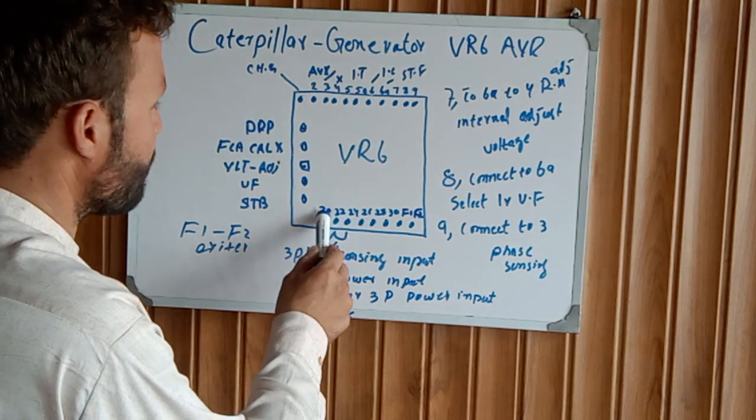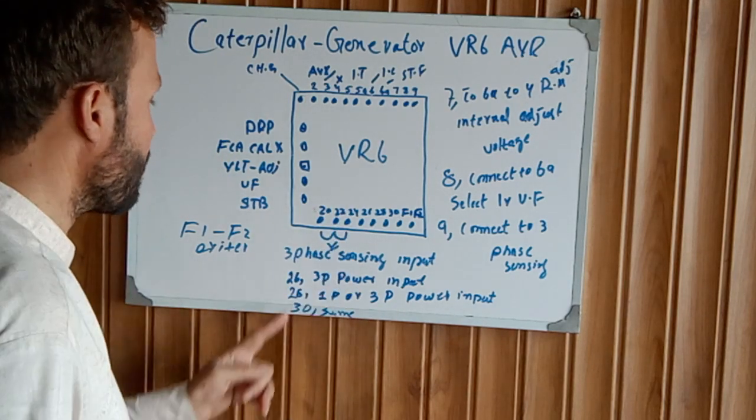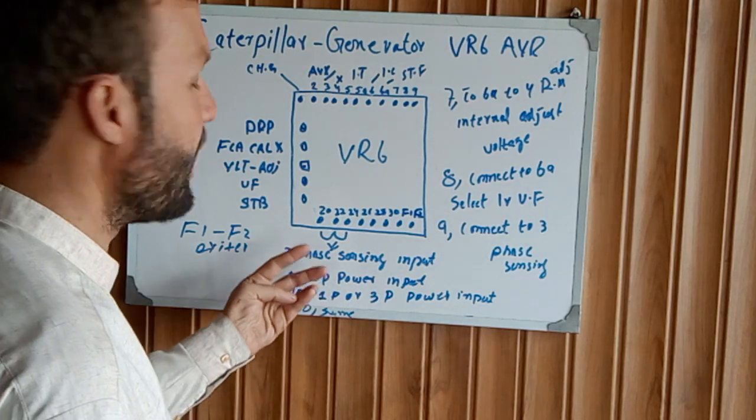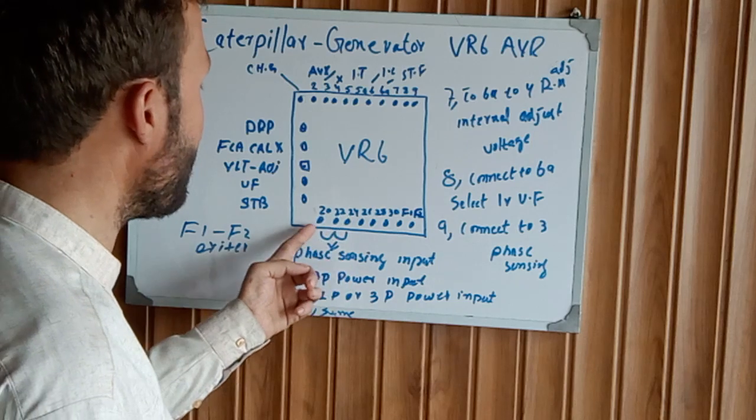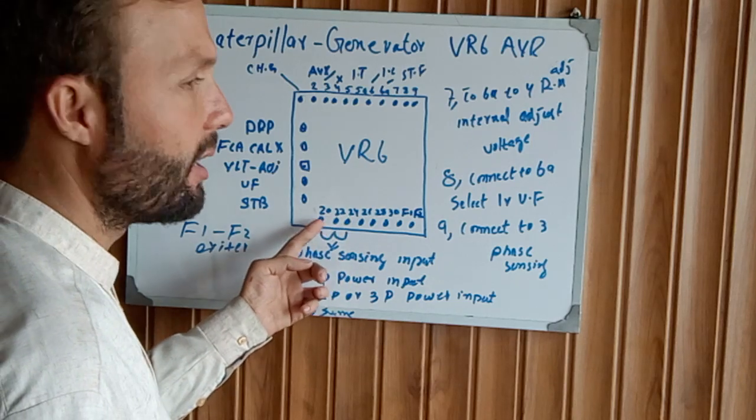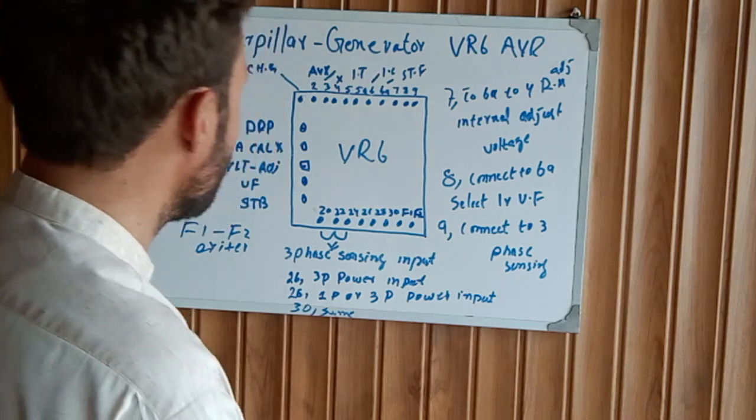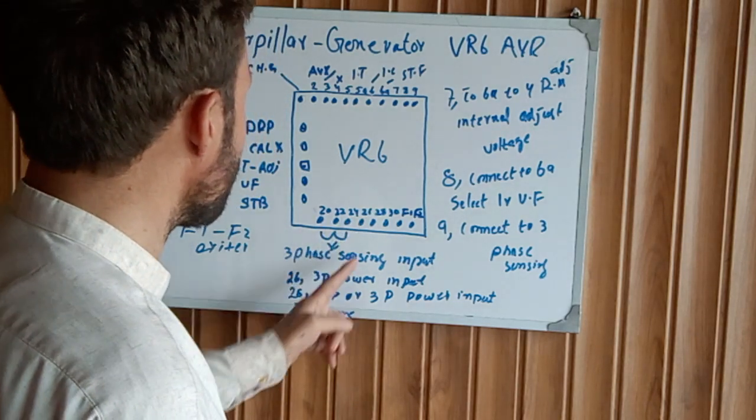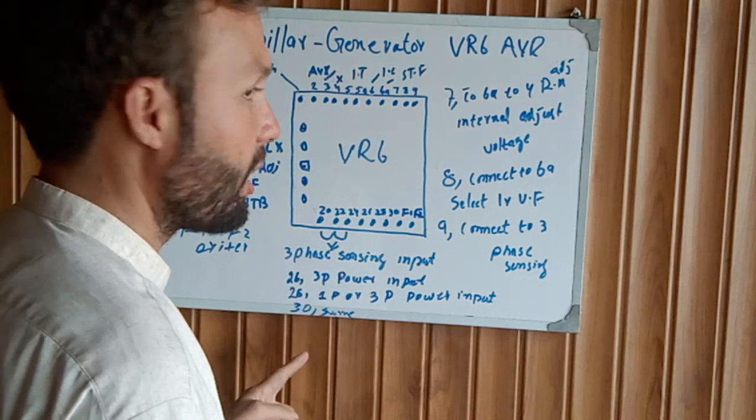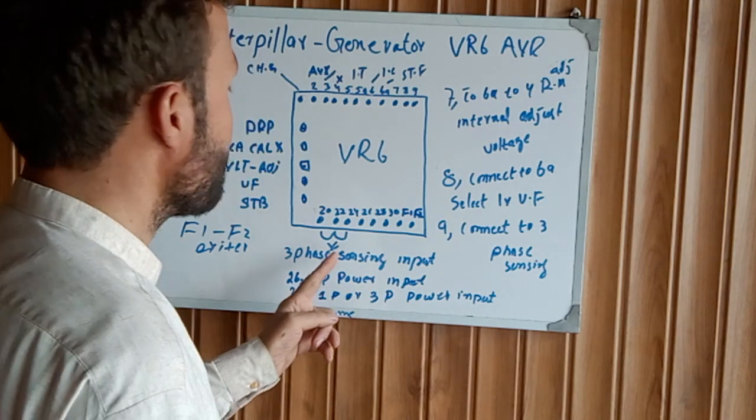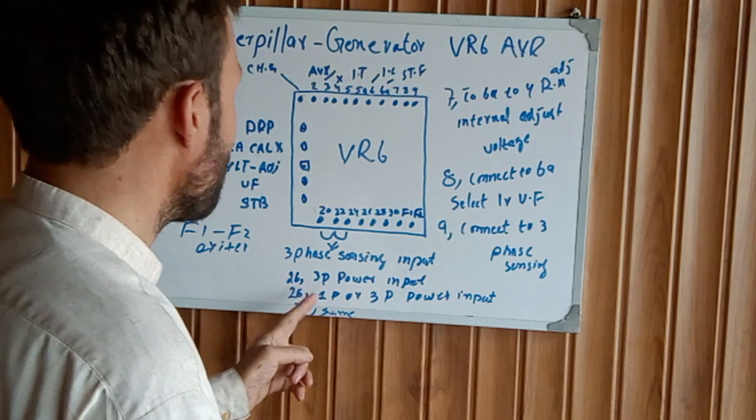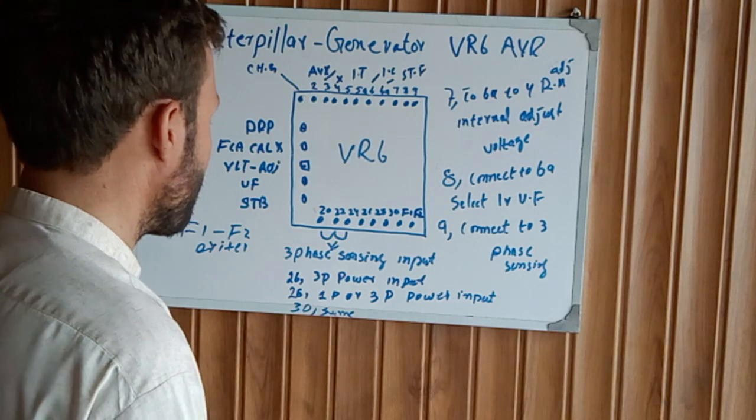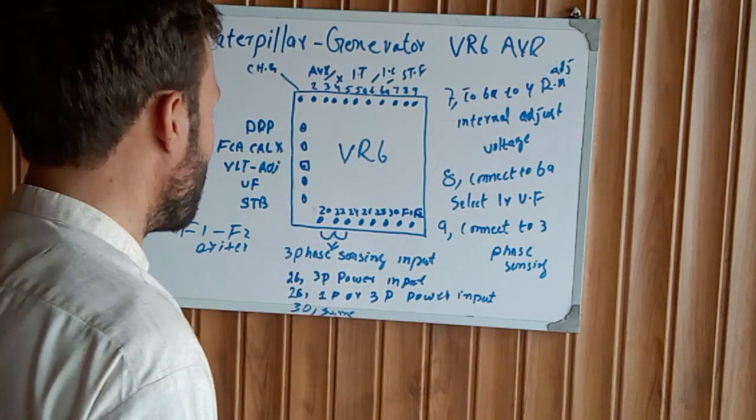After that, there is 20, 22, and 24. Three-phase sensing input. Like L1, L2, L3. Like A, B, C. Like X, Y, Z. Three phases of the alternator input sensing. 26, three-phase power input. Take one wire from the phases and connect to the 26 three-phase power input.